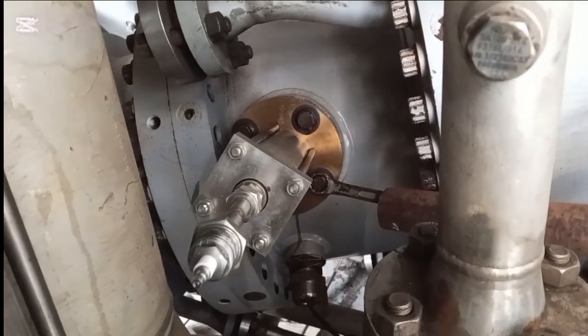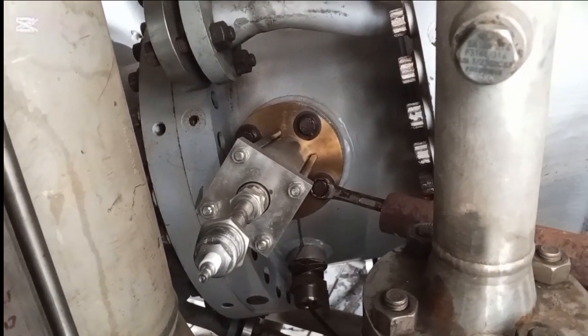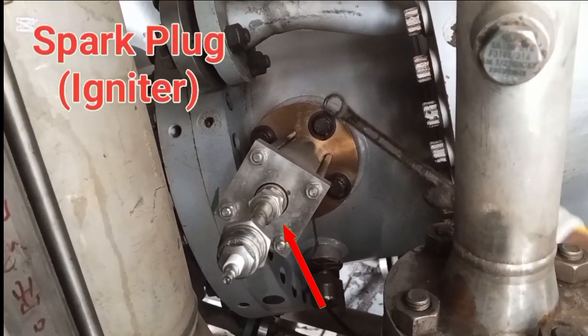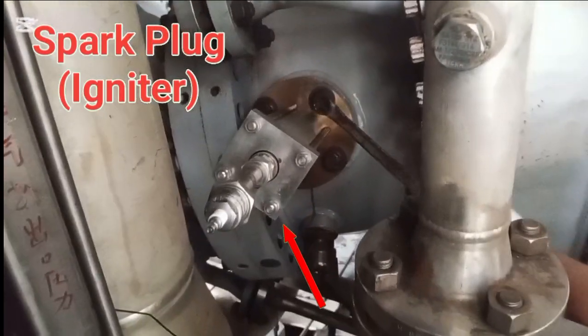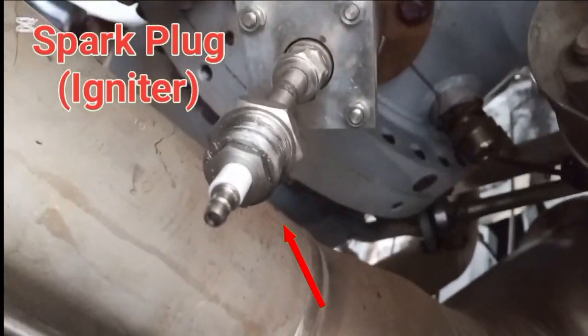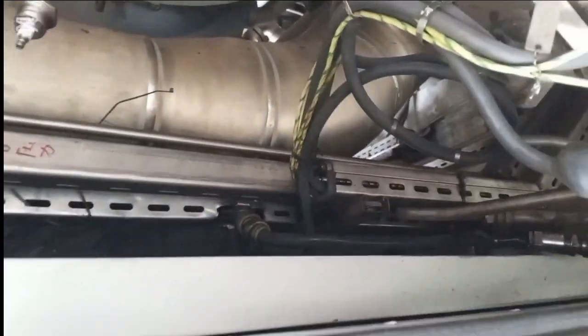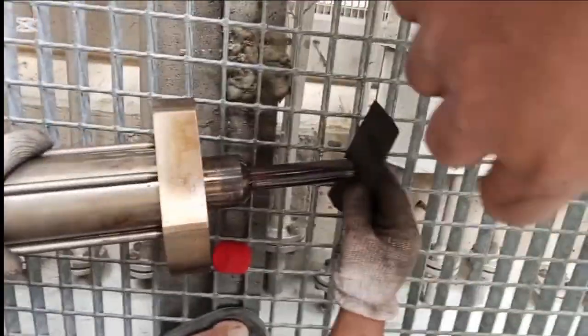For ignition, there is a high voltage transformer, and the output of this transformer is 2 into 3000 volt AC, but the spark plug needs 3000 volt DC. So here a capacitor and a control circuit are used. This is the spark plug, and you see there is an electrode inside the spark plug.